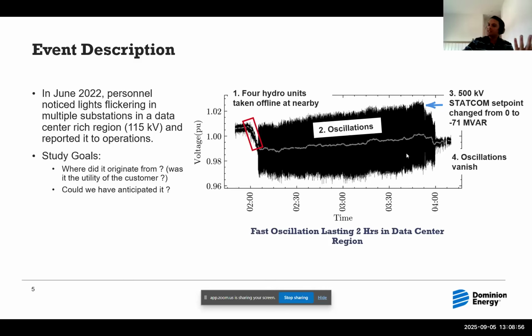There were some coincidences in this, because 5 minutes before the oscillations vanished, someone had changed the reactive power set point on a nearby STATCOM. So people thought maybe the STATCOM saved us, or had a role in damping this oscillation, which is difficult to establish given there's a 5 minute difference between when they changed the operating point and when the oscillation vanished. So the goal of our study was to understand where it originated from.